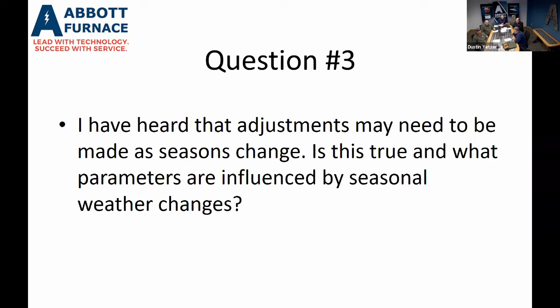What happens is the weather gets colder and everybody closes the doors, windows, and garage doors in the buildings. The air is still trying to force its way into that building, and a lot of times the easiest path it has is down your furnace stacks from the roof. So we end up getting some air ingress through the rear stacks, sometimes through the front stacks. That'll get air in the furnace and you'll start seeing quality issues, discolored parts. And yes, there are things we have to do.